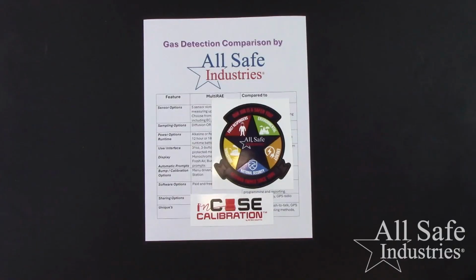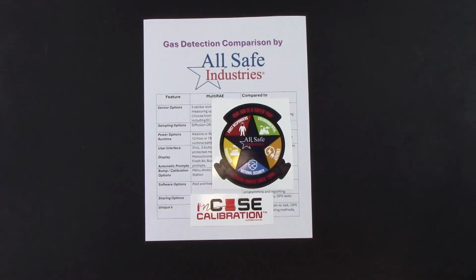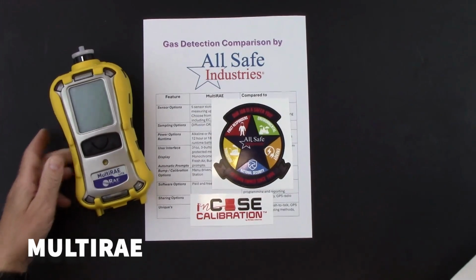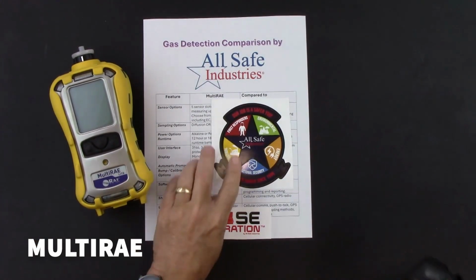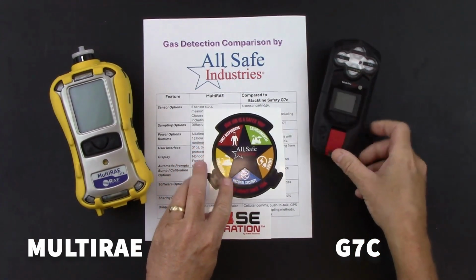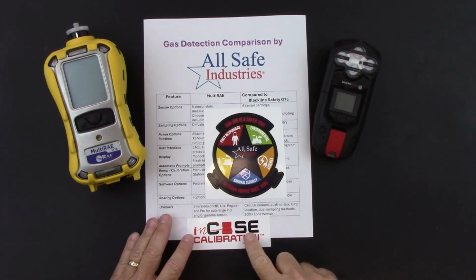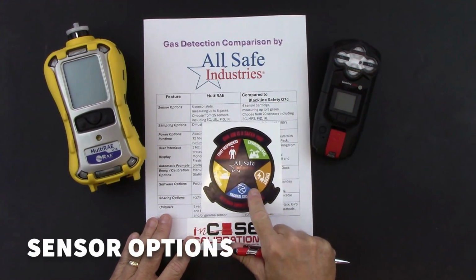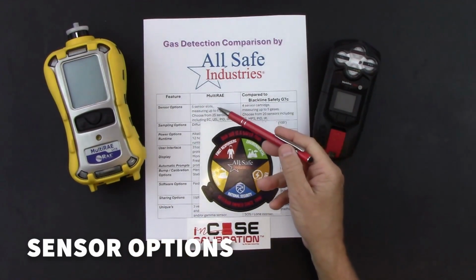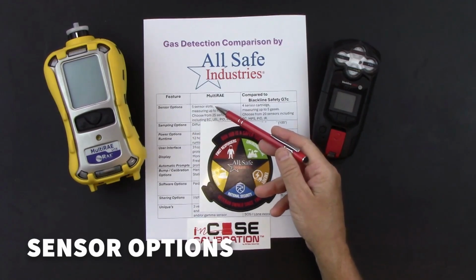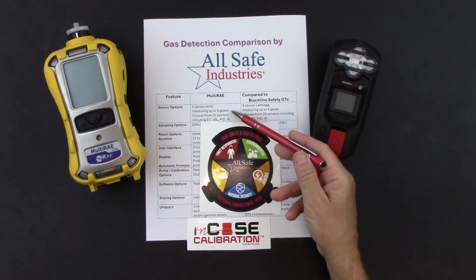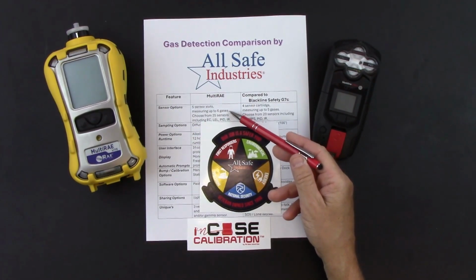Let's begin. In this multi-gas comparison video, we'll compare the MultiRAE from Honeywell to the G7c from Blackline Safety. First thing we'll talk about are the sensor options. So with the MultiRAE, we have 5 different sensor slots measuring up to 6 different gases. We can pick up 2 gases with 1 combination sensor for CO and H2S.